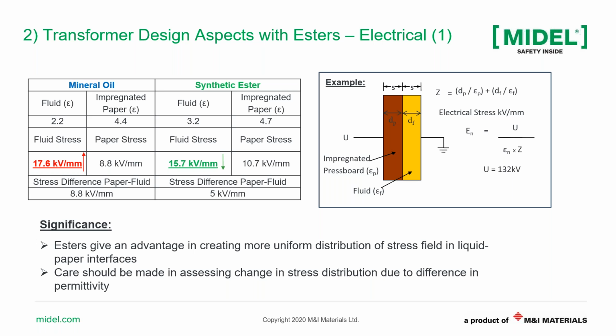Now, let's shift our attention to the figure. On the right-hand side, you see the example there. Basically, you have two rectangles. One is the pressboard and one is the liquid. So because of the permittivity difference, the electric field stress is distributed proportionally between this solid pressboard and the liquid. Our interest in a transformer is to reduce the stress in the fluid gap and increase the stress in the solid impregnated insulation because the solid insulation is stronger than the fluid.